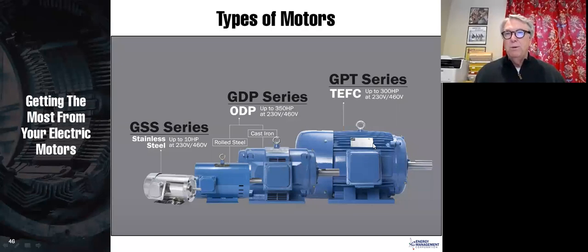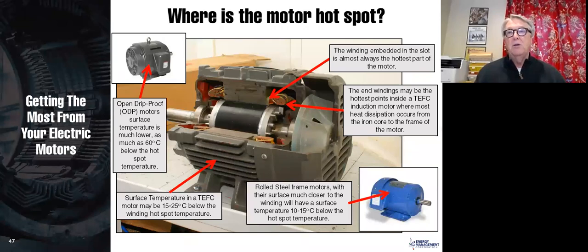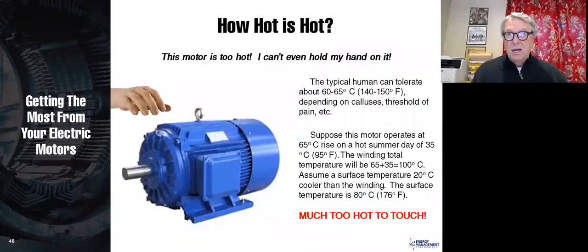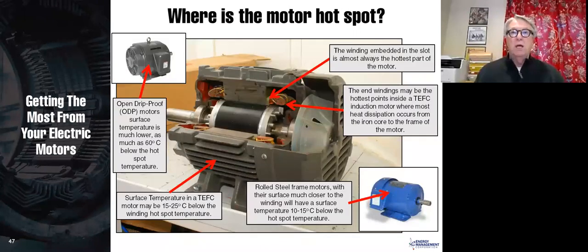This is the workhorse. This is what most people use, a totally enclosed fan cooled. It is cast iron, so it's very stiff, keeps the bearings in alignment, and it's got a fan here under this cover on the back. The fan blows air over the outside of the motor rather than the inside of the motor, and therefore much better for dirty applications. This will be our last slide, and I think it's actually maybe 2 more slides.